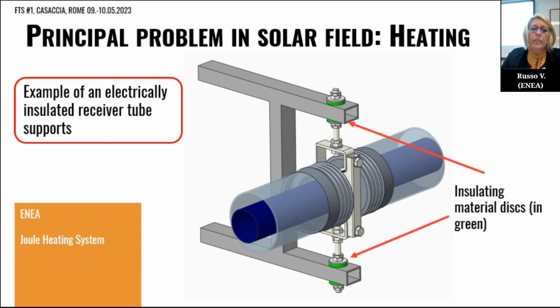Okay, it must be kept in mind that the components subject to electric heating, since they are crossed by the electric current, must be isolated from the rest of the structure. In particular, the support of the receiver tube, because the Joule effect is applied on the receiving line. So in this picture, we can note the green disc positioned between the tube and the structure. These discs are made of electrical insulating materials. In general, the material is a ceramic like alumina, zirconia, or something like that.